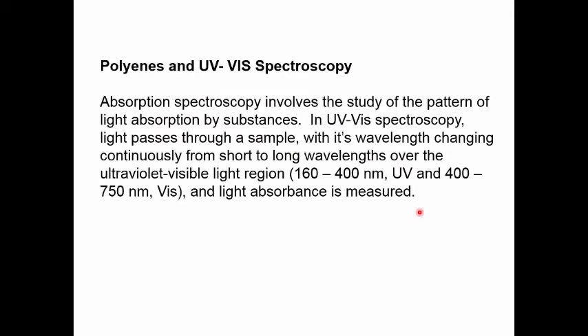Absorption spectroscopy involves the study of the pattern of light absorption by substances. In UV-Vis spectroscopy, light passes through a sample. The instrument will change the wavelength continuously from short to longer wavelengths. It scans the region from 160 all the way up to 750 nm. The ultraviolet region is from 160 to 400 nm and the visible from 400 to 750 nm. And over that whole range, the instrument measures regions where light is absorbed.